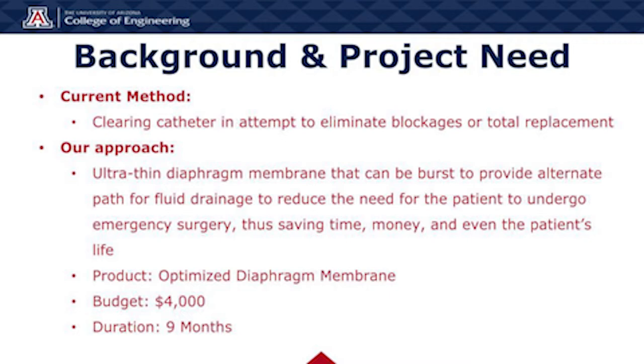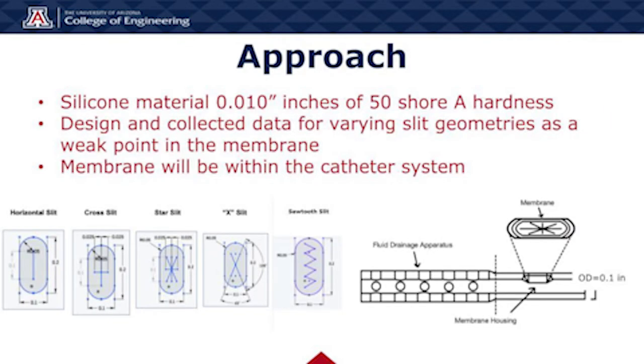Our product is the optimized diaphragm membrane. The budget is $4,000 for this project and the project duration is 9 months. Our approach was to create an ultra-thin membrane 0.010 inch thick using a silicone rubber with a hardness of 50 on the Shore A scale. The membrane will be implemented in a catheter system and will be located in the membrane housing, as shown in the figure on the bottom right, just following the main fluid drainage apparatus.